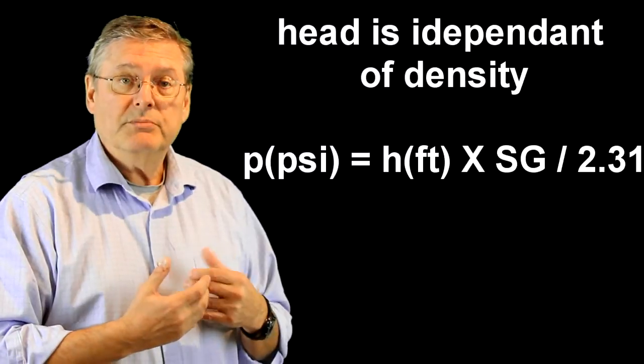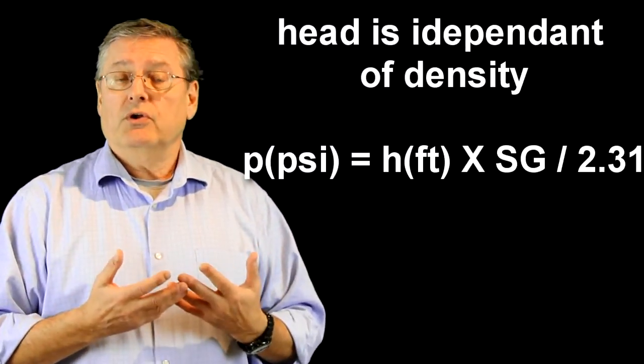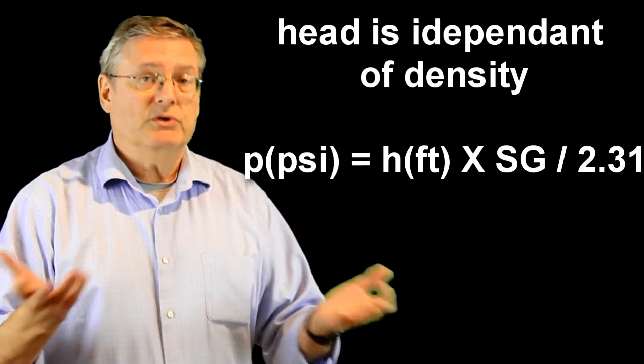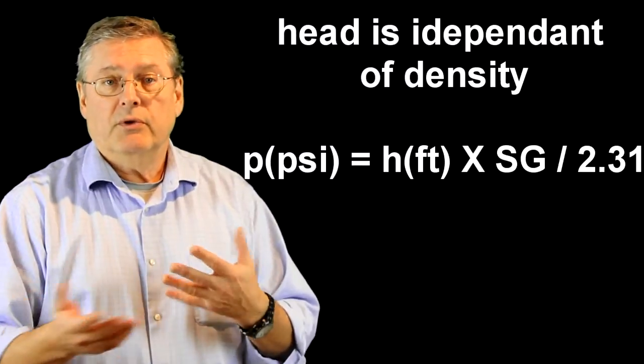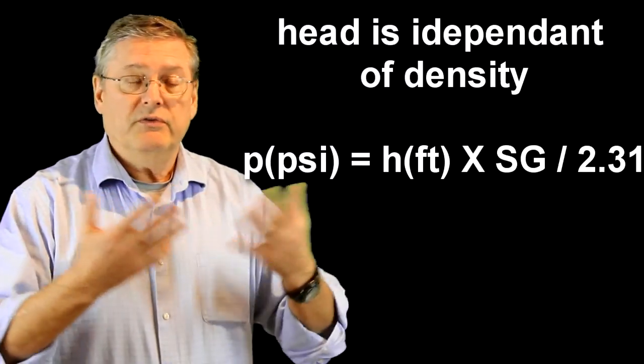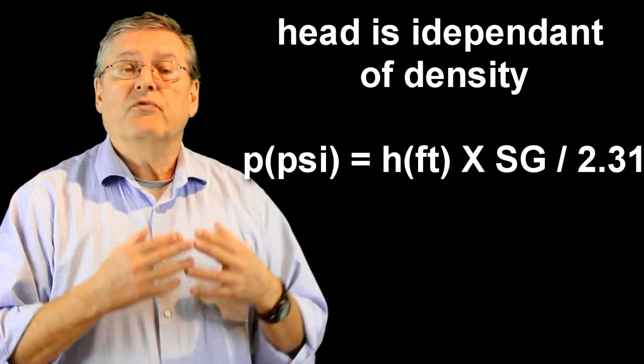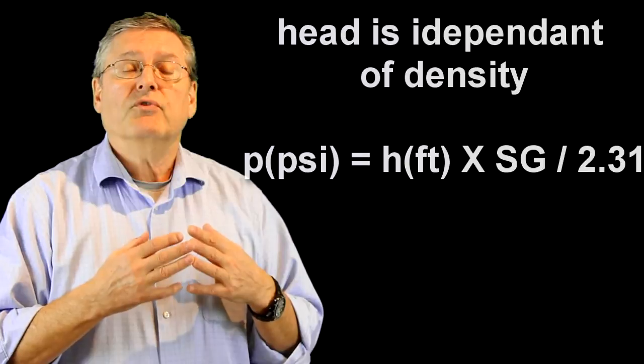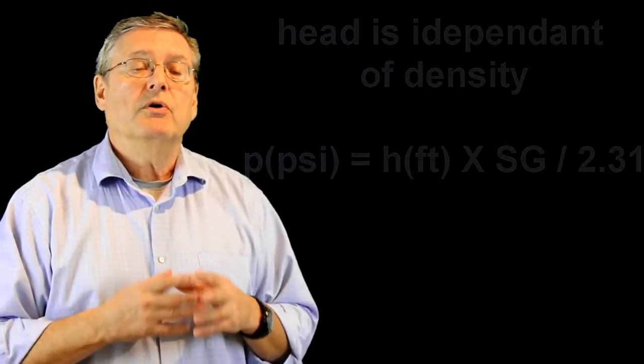Head is not. Pressure does depend on density, so that's equally very good for the manufacturer because he doesn't know what type of liquid you're going to be pumping. You could be pumping oil, you could be pumping a heavy slurry. From his point of view it doesn't matter; his number of head is independent of the density of your liquid. So that's also a very good reason that makes it attractive for him to use head as the main characteristic of centrifugal pumps.